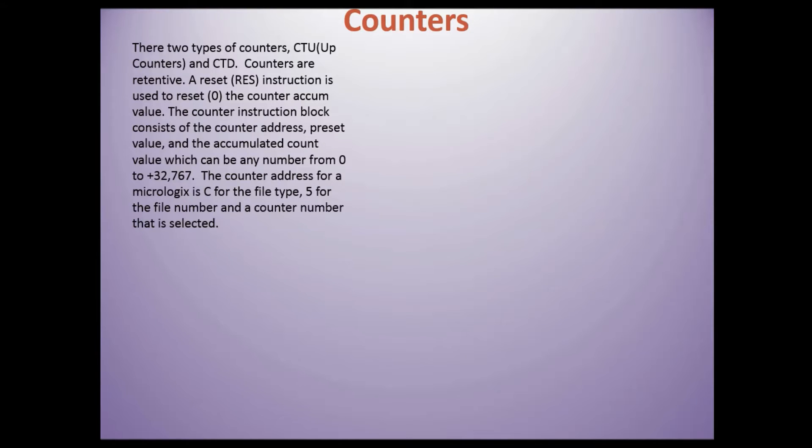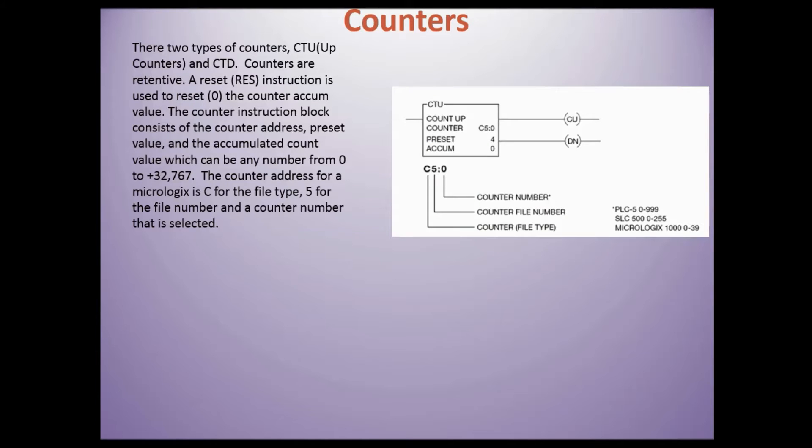There are two types of counters: CTU, the up counter, and CTD, the down counter. Counters are retentive. A reset instruction is used to reset the cumulative value to zero. The counter instruction block consists of a counter address, a preset value predetermined by the operator or programmer.